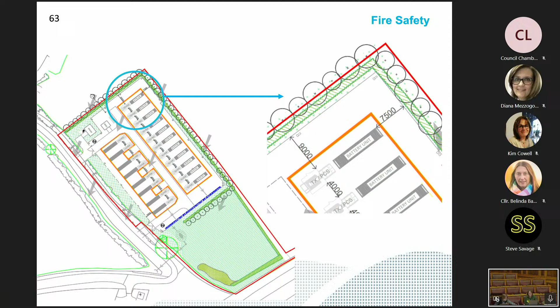In respect of distance to residential properties, the NFCC guidance notes that distances between BESS units and occupied buildings' side boundaries will vary. It recommends an initial minimum distance of 25 meters prior to any mitigation and notes that reduced distances may be possible in rural settings. In this case, the closest residential properties are located between 140 and 150 metres away from the BESS compound. This indicates the site is appropriately sited in relation to residential properties, and it is considered to accord with the guidance.